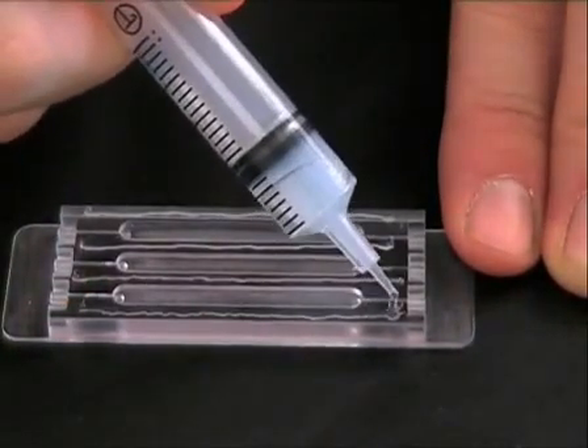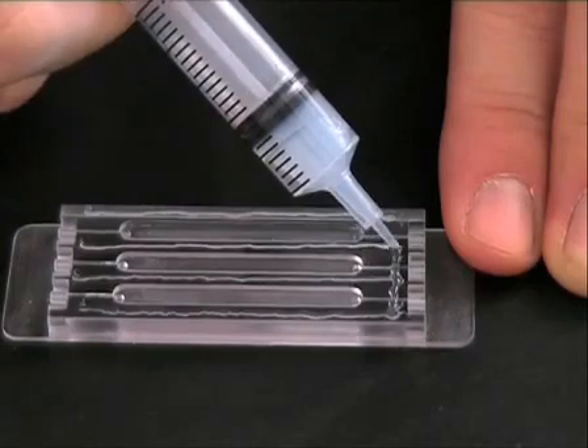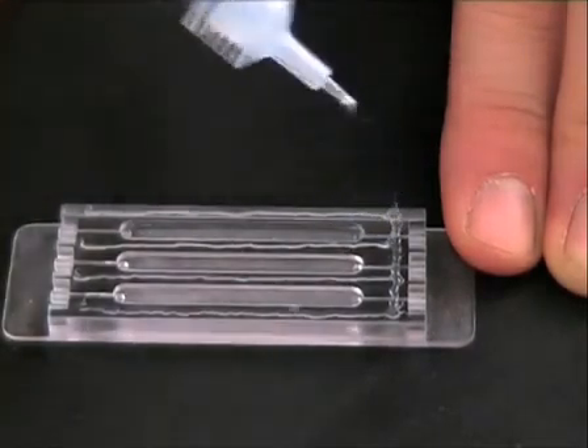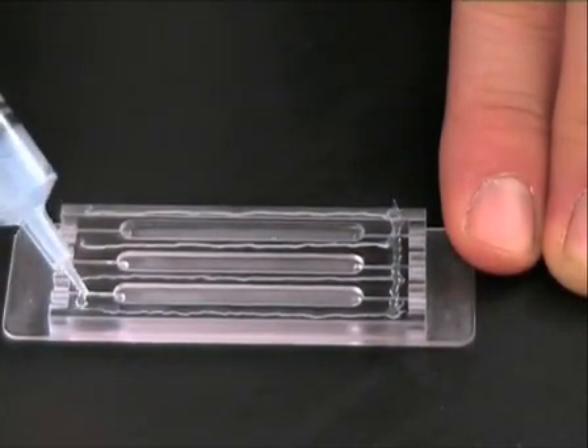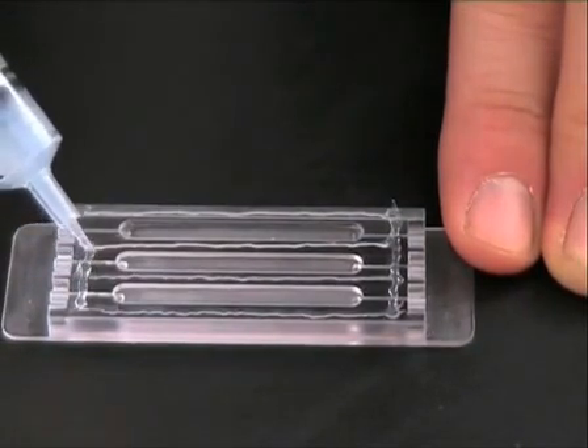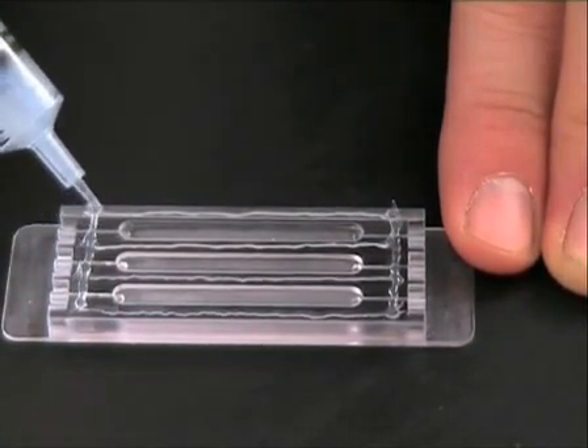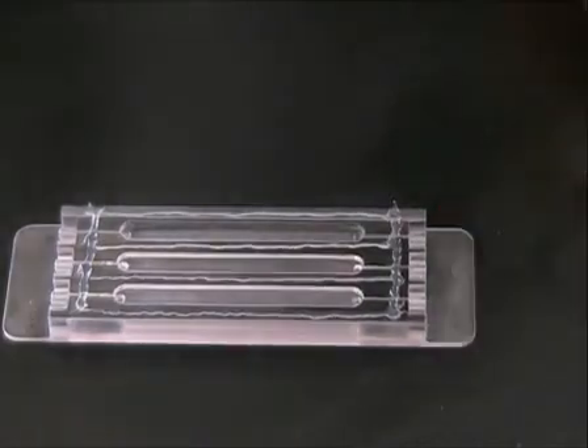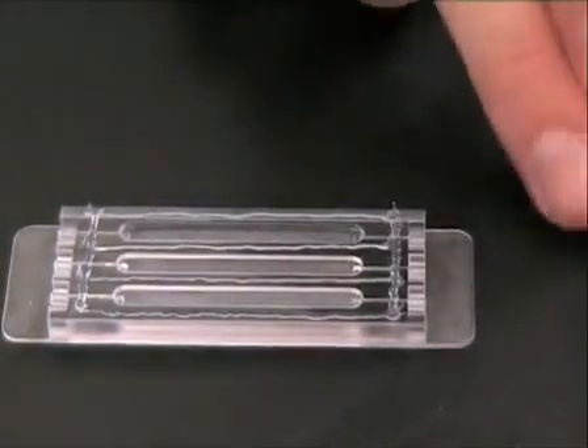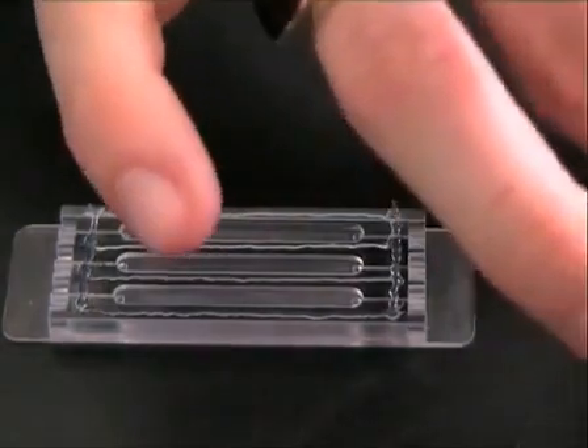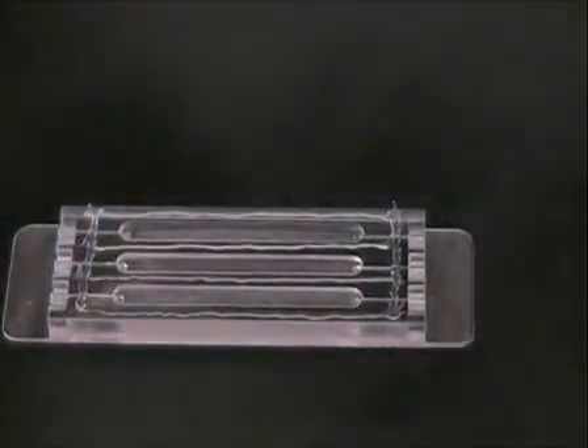When applying silicone in the opposite direction, make sure not to scratch out the already made lines, but try and gently lift the tip as you go across. In this way, you will make sure that no openings in the silicone lines will lead to leakages between the chambers or from out the flow cell.